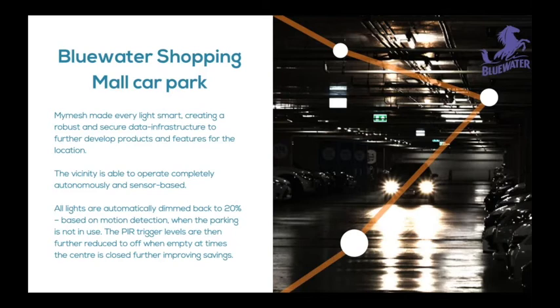And this setting proved so popular with the client, they then asked us to implement this throughout the centre at different times of the day. So now at 6 in the morning, the centre will run 50% and 20% unoccupied, but at 1 o'clock in the morning, it then goes to the setback period where it's 50% on and then 0 off. So therefore they're saving that 5 hours of additional energy, rather than leaving them all running at 20%.